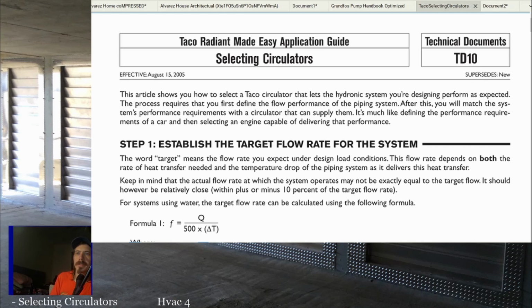When you're doing a circulator, like if you're replacing a circulator on a boiler, it's extremely important that you get a pump that has the same performance. So a lot of times you'll usually see either B&G pumps on a boiler system, or you'll see Taco 007s or Grundfos or something like that. And those things aren't necessarily interchangeable. They're starting to come out with multi-speed. Grundfos has had multi-speed circulators for residential and small applications for a while now, and Taco's got a variable speed pump, which will handle things like that pretty well now. But it's like anything else. If you're replacing a single speed pump with a single speed pump, then you need to make sure that it can handle the flow rate that you want and the head pressure that you have to overcome. If you have no idea what kind of pump a system needs, then it's important that you be able to size one.